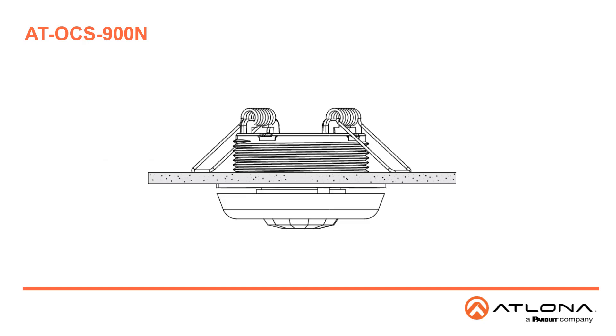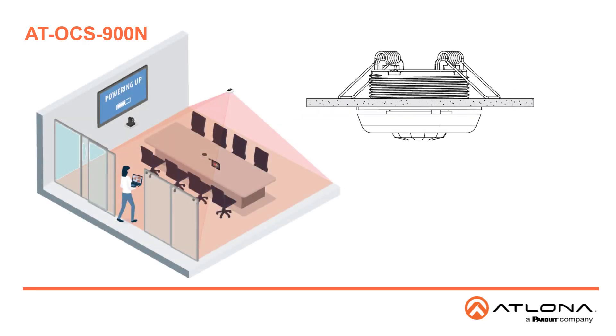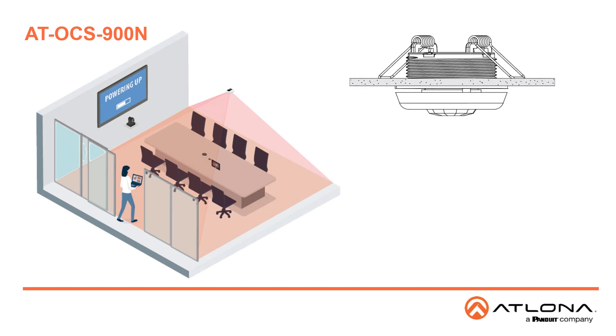This ceiling-mounted sensor uses passive infrared technology to detect occupancy in the coverage area. It comes with two lenses that cover approximately 900 or 2,000 square feet, depending on ceiling height. A blinder insert is included that limits the sensor's field of view, preventing detection in unwanted areas such as doorways or windows with heavy cross-traffic.